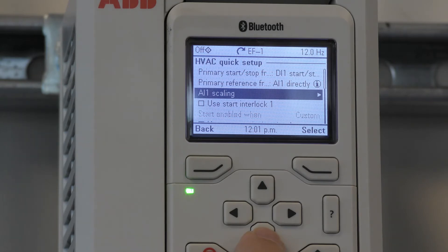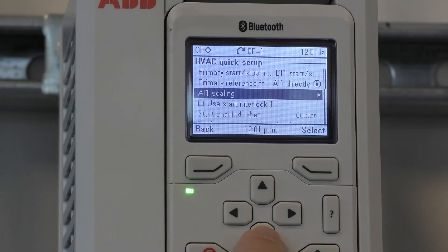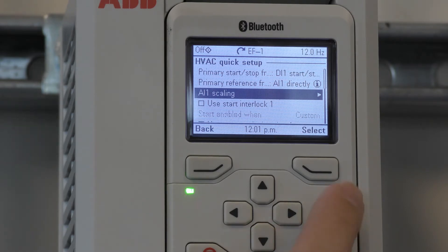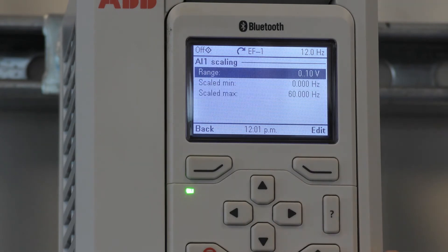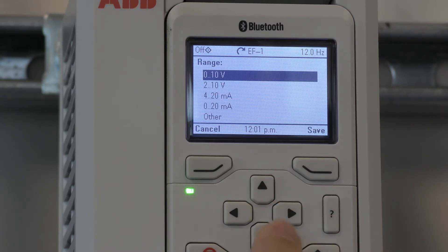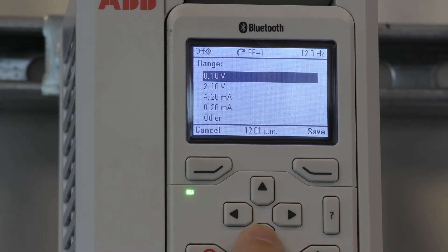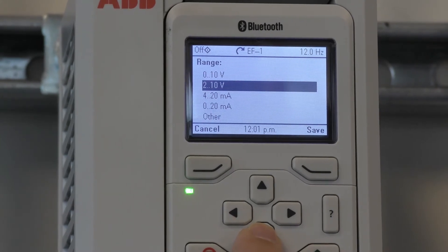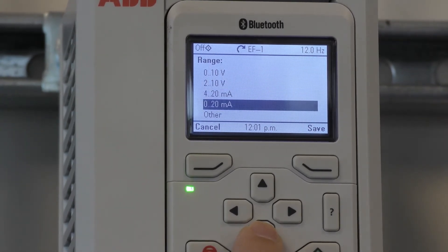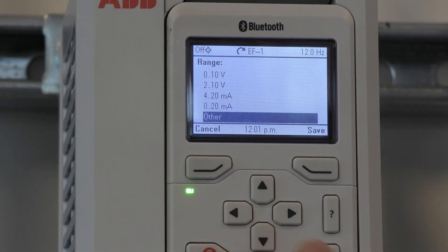AI1 Scaling is where we can select whether we're going to use a voltage analog input or a milliamp analog input. Also, if we're going to utilize serial communication such as embedded fieldbus or a fieldbus adapter. The range options are 0 to 10 volts, 2 to 10 volts, 4 to 20 milliamps, 0 to 20 milliamps, or other.